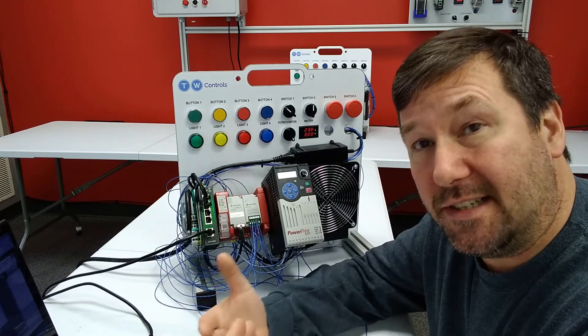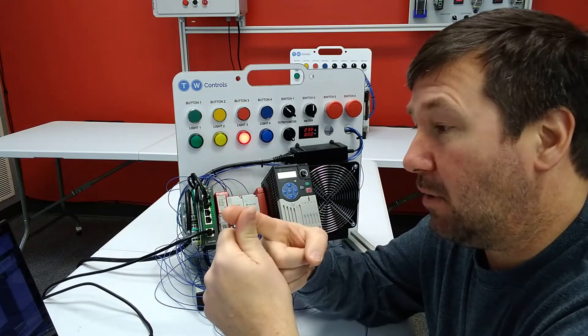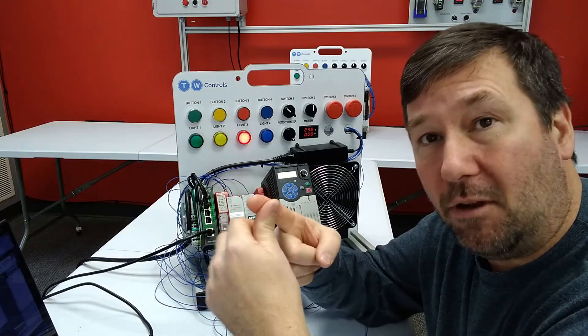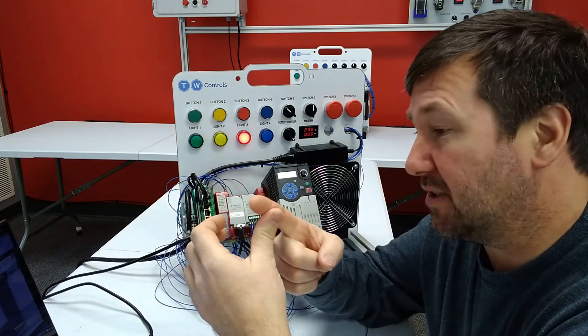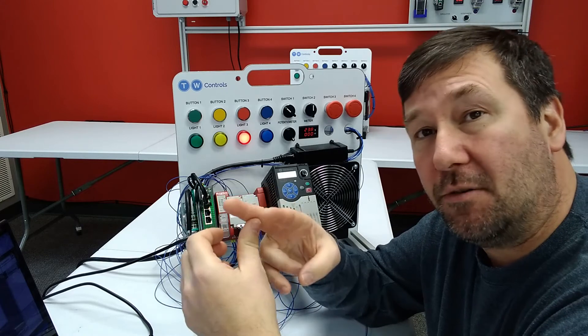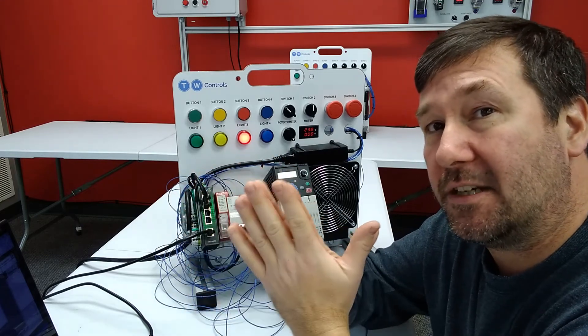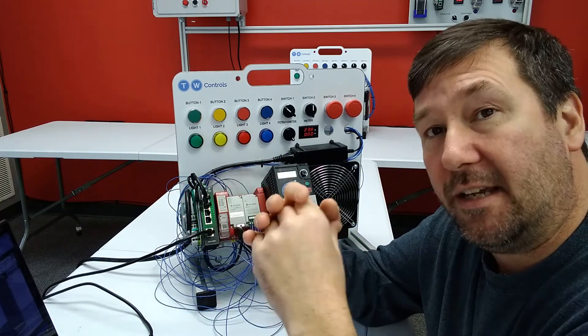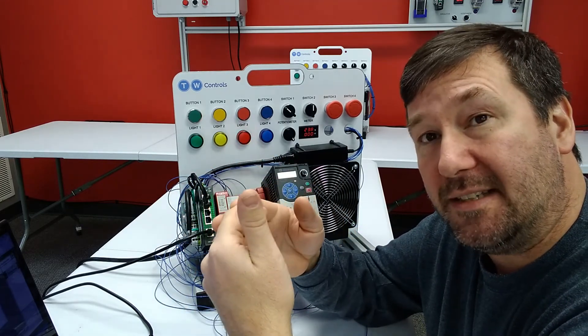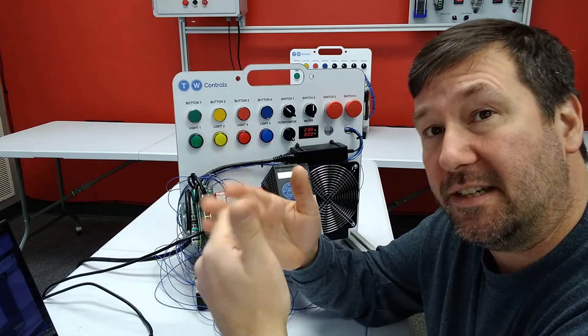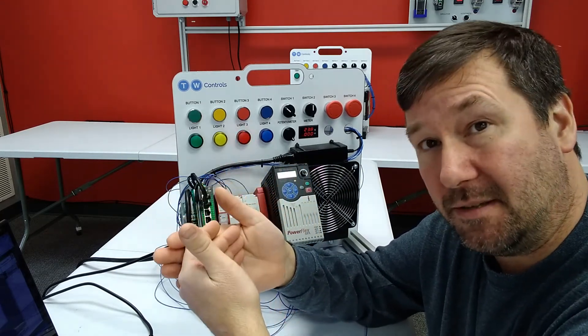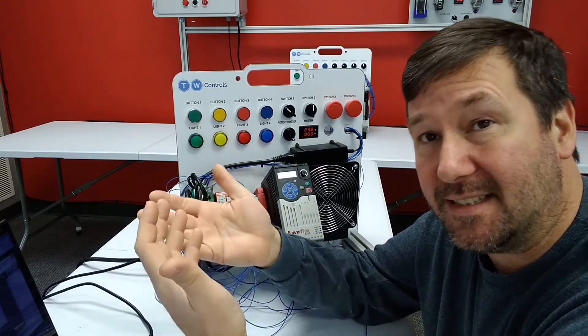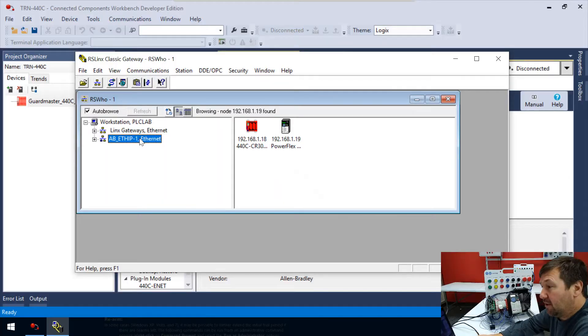Now, let's say yours didn't show up. There are a lot of reasons it couldn't. You could have a firewall that blocks the packets that are used for discovery, you could be going through a router. In those cases, you need to tell the PC or RSLinx, where do you want me to go look and see if there is a PLC? That's the difference. Let's go ahead and configure that one.